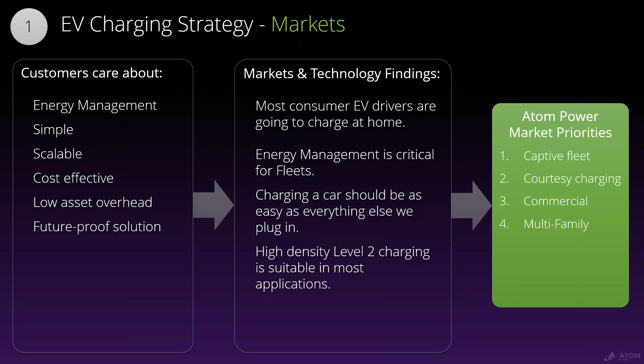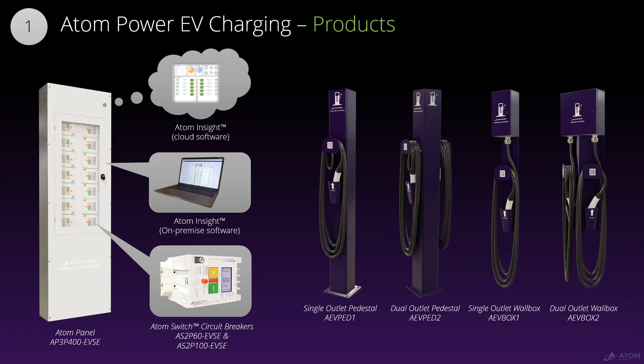And so to do that, we took our 400 amp panel and got a UL listing for an EV specific version of our breaker. And that allows it to communicate with a pilot signal out to these pedestals. And you've got a single or double pedestal that you put in the ground in a parking lot, or a single or double wall box that you'd put on the wall in a garage. And again, there's no smarts out here and you're exposed to the public. So there are some huge benefits there. Now all of your smart stuff is in the building, maybe in the electrical room, away from the public, away from the weather events, vandalism. You can choose a 48 or an 80 amp. 80 amp is the highest rating for level 2 charging. And again, it's programmable. So if you want it to be less than that, it can be less than that.